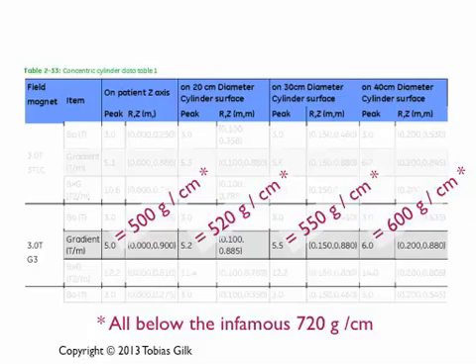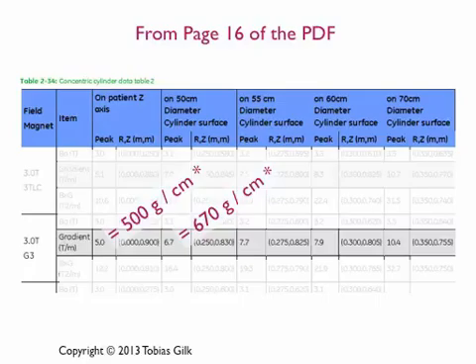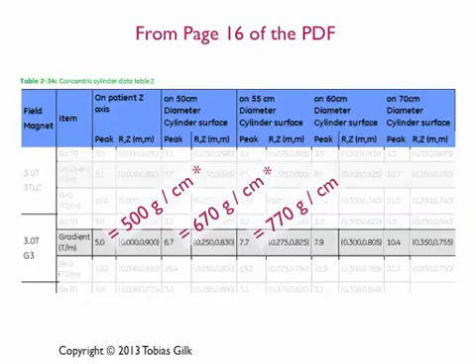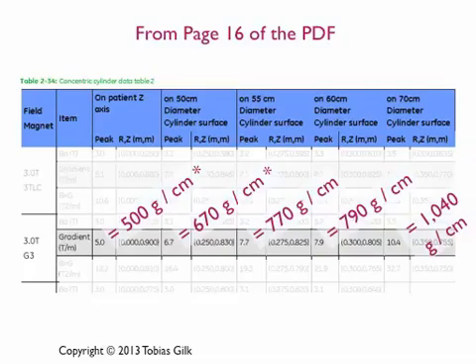That magnet's bore diameter is greater than 40 centimeters, so where's the rest of the data? Unfortunately, you have to jump to page 16, where there's a whole other chart. They start again with the Z-axis value of 500 gauss per centimeter, then pick up at 10-centimeter increments. At 50-centimeter diameter (25 cm radius), the spatial gradient is 670 G/cm. At 55 centimeters: 770 G/cm. At 60 centimeters: 790 G/cm. And lastly, at 70 centimeters — the wall of the bore, since this is a 70-centimeter diameter magnet — the spatial gradient is 1,040 gauss per centimeter.